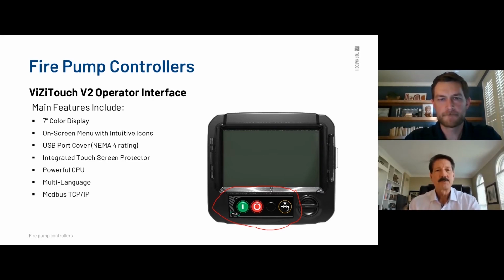But we have pump room temperature as standard with our unit. So that temperature sensor is embedded right there in the face, as he's got circled. And that's huge a lot of times, especially for diesels, but electric sometimes too. Whoever thinks that the pump room is going to drop below freezing, and then all of a sudden you have a bad pressure transducer, and it comes to find out that, oh my goodness, it shows low ambient temperature. It was actually below freezing. No one would know that for a day or two, but it could help. Again, this is where the data logging, especially with pump room temperature, will help you determine what the problem was.